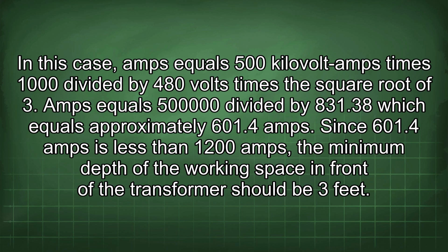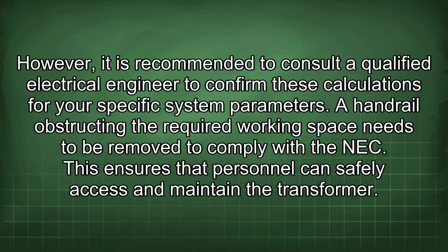Amps equals 500,000 divided by 831.38, which equals approximately 601.4 amps. Since 601.4 amps is less than 1200 amps, the minimum depth of the working space in front of the transformer should be 3 feet. However, it is recommended to consult a qualified electrical engineer to confirm these calculations for your specific system parameters. A handrail obstructing the required working space needs to be removed to comply with the NEC. This ensures that personnel can safely access and maintain the transformer.